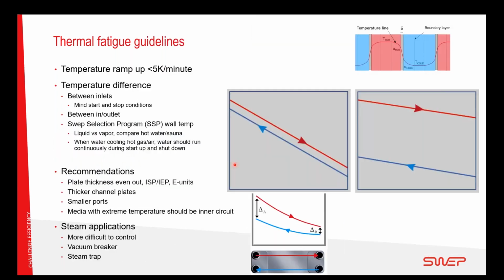Some guidelines we have taken from experience here. The most important is to avoid the thermal shock. We have a ramp-up time estimated to be about 5 Kelvin per minute to make sure everything is heated up nice and slow. We have the temperature difference, and there are 2 ways to define it. It's between the inlets. So if you have a high temperature difference between the 2 medias, you should always have this slow ramp-up time. Then we have also between the in and outlet in the heat exchanger.